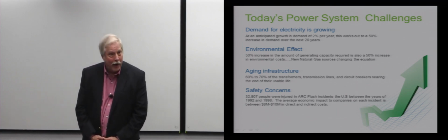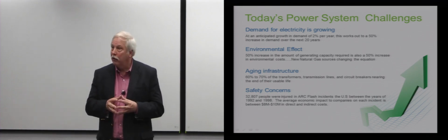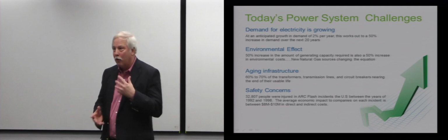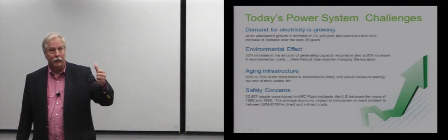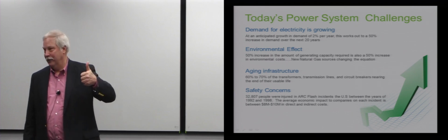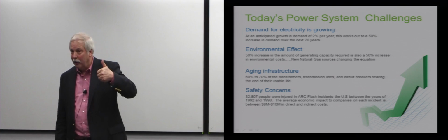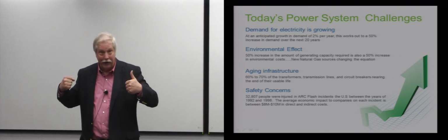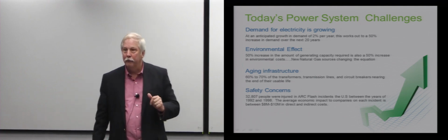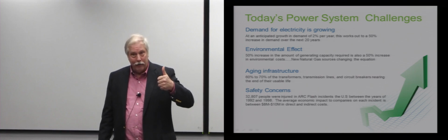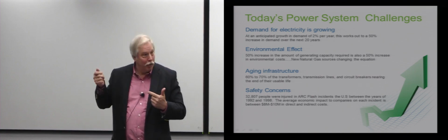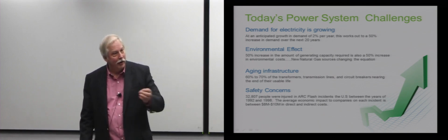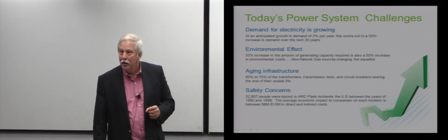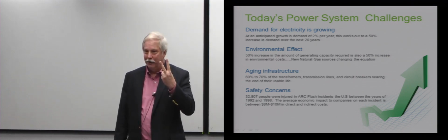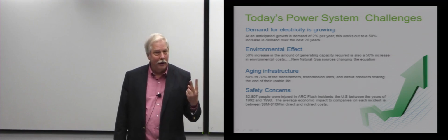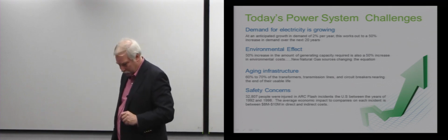There are new technologies now that can actually detect an arc flash. If you think about the characteristics of an arc, number one, it has bright light, so light becomes one of the primary detectors of an arc flash. This is like when a circuit breaker is told to open and doesn't quite get there, and it kind of blows out the front door. Detecting light is very fast, but turning on a light in the room is also light, so how do you differentiate a flash from a light turning on? Well, an arc also has sound. By correlating sound and light, you get another mechanism for detecting arc flash in a piece of electrical switchgear.